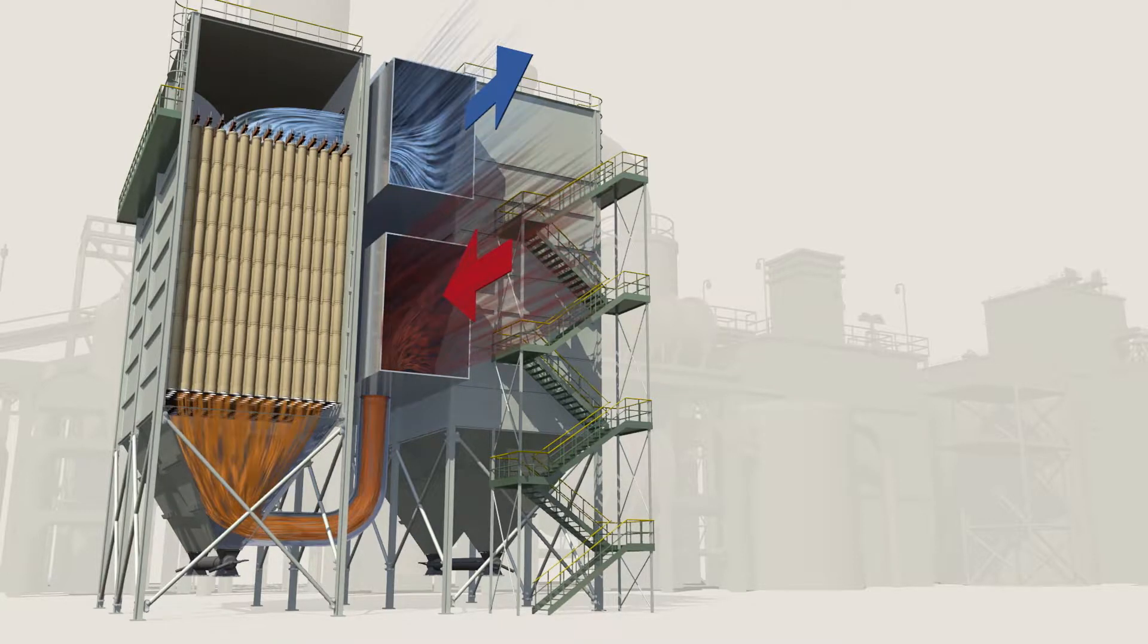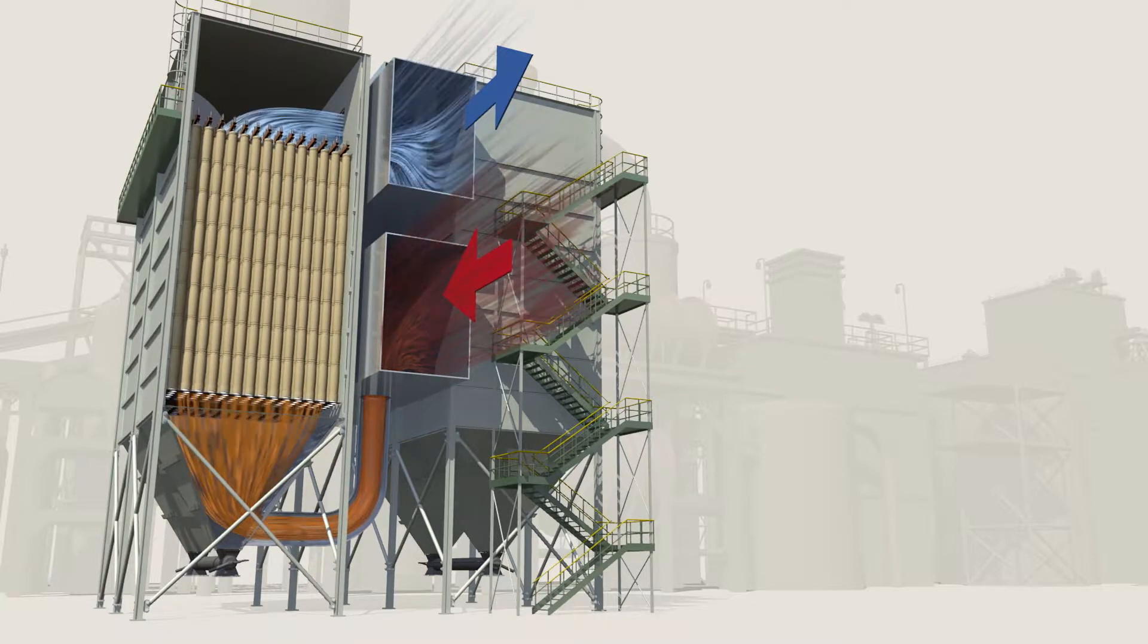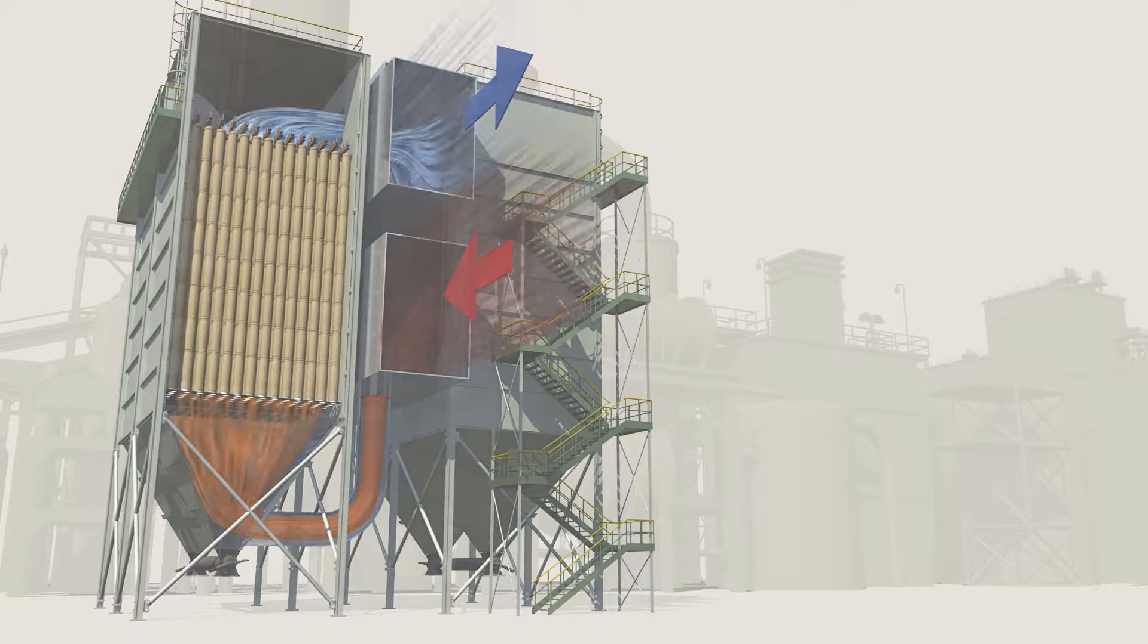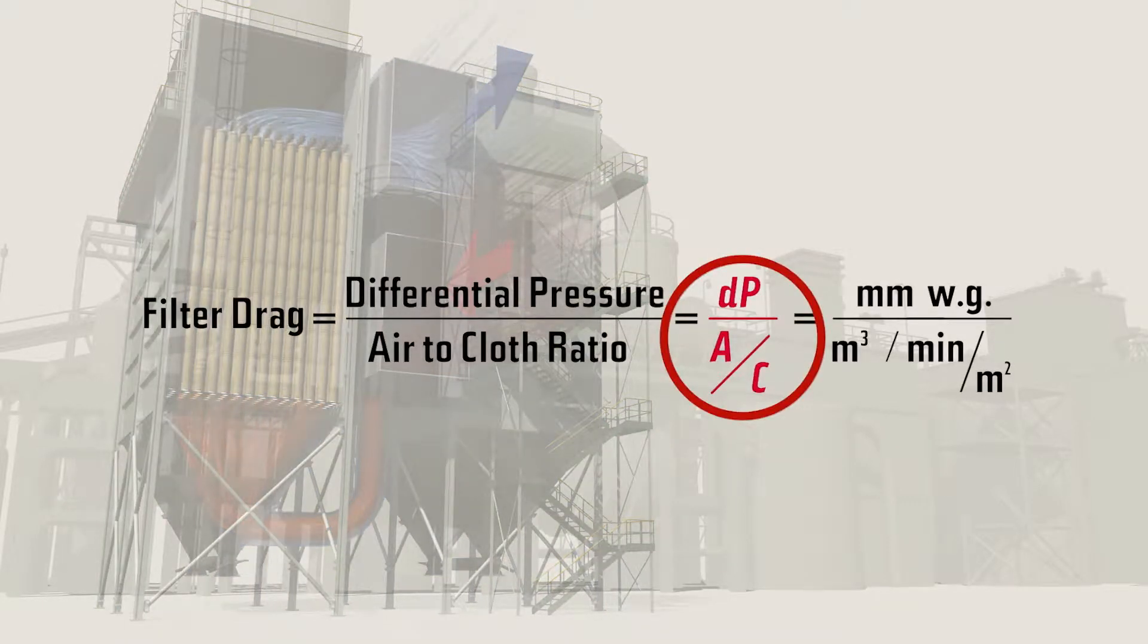The higher the resistance, the more energy consumed to move the air through the baghouse. This formula breaks it down: filter drag equals differential pressure divided by air to cloth ratio.